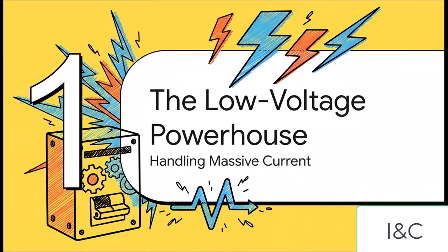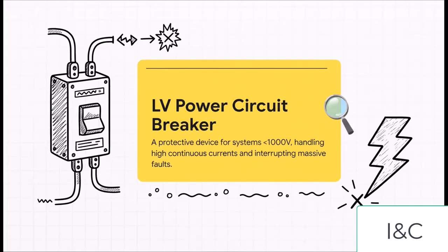You know, that brings us to the name low voltage, which is actually a little bit misleading. Because while these devices do operate in systems under 1,000 volts, the sheer amount of current they have to manage is anything but low. They are true, bona fide powerhouses. So what is it exactly? Well, at its core, it's a protective device. It's designed for electrical systems running under 1,000 volts, and it really has two main jobs.